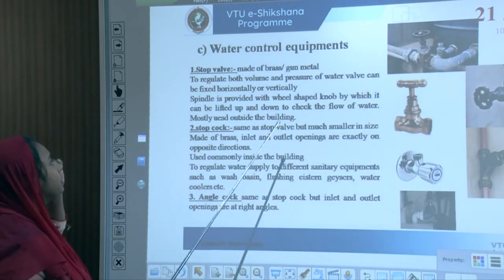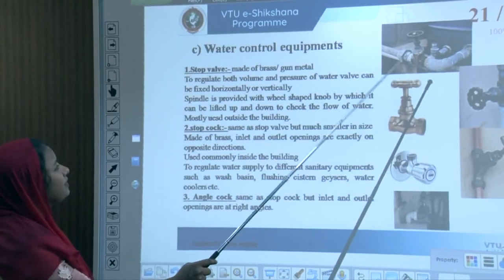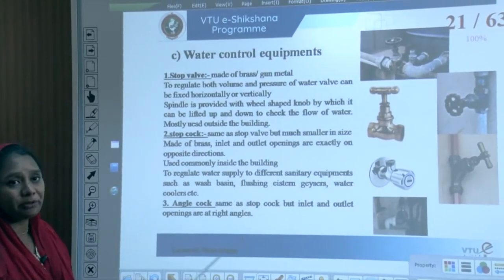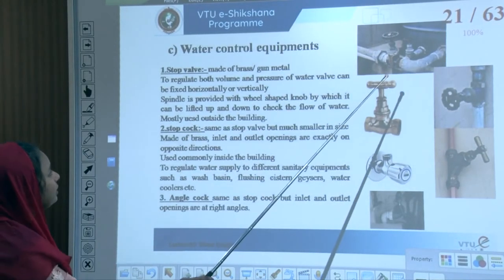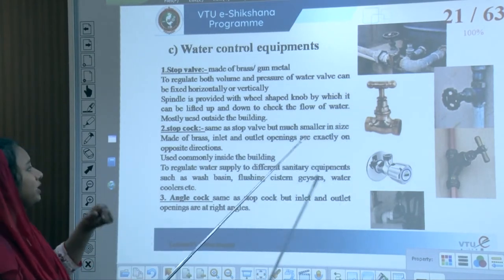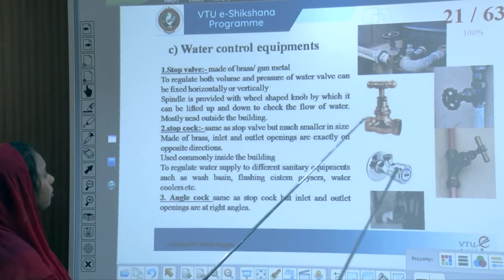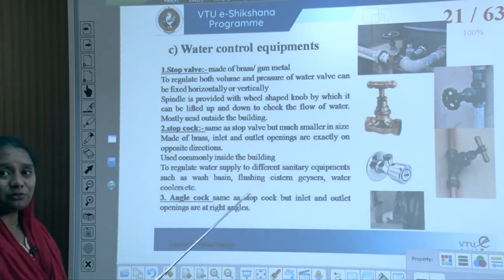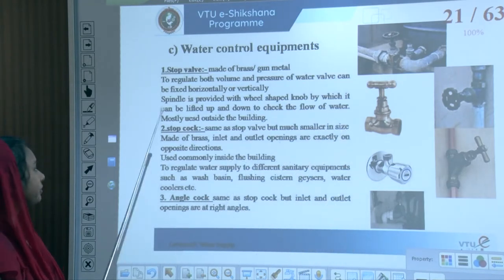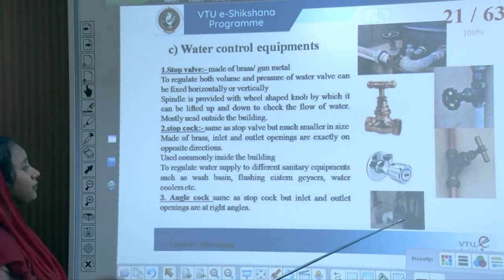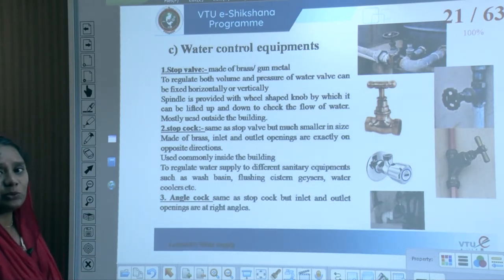Control equipment includes: a stop valve, which is a gun-metal device that regulates both the volume and pressure of water and can be fixed horizontally or vertically. It has a spindle with a wheel-shaped knob to lift up and down to check the flow, and is mostly used outside the building. A stopcock is the same as a stop valve but much smaller, made of brass, with inlet and outlet openings in exactly opposite directions. It is commonly used inside buildings and regulates water supply to sanitary equipment such as wash basins, flushing cisterns, geysers, and water coolers.